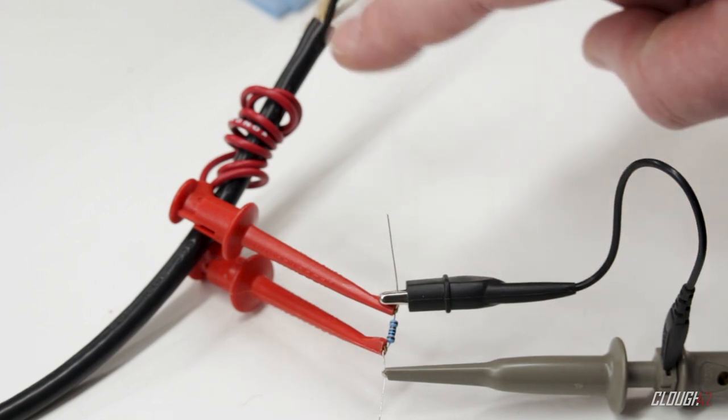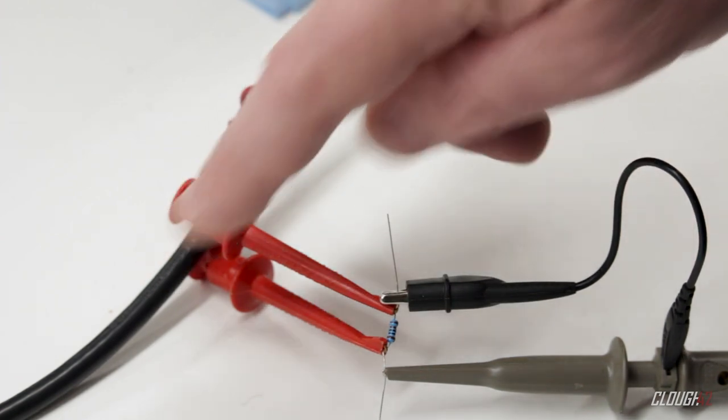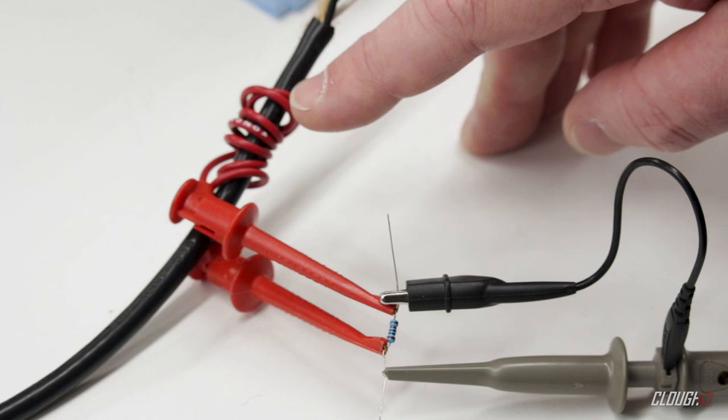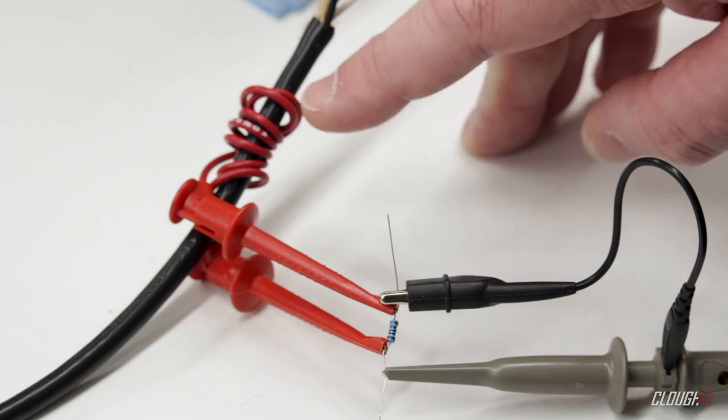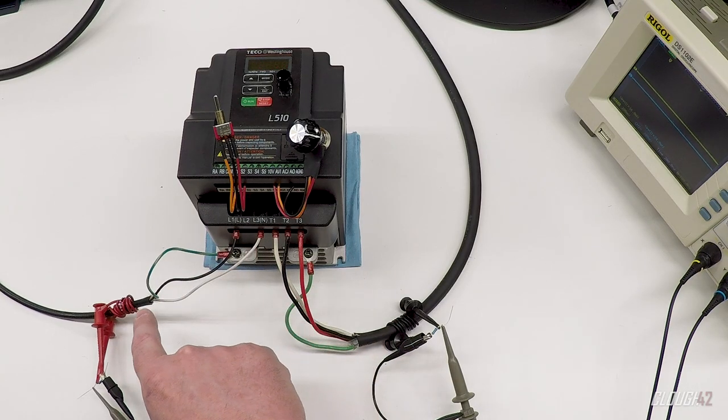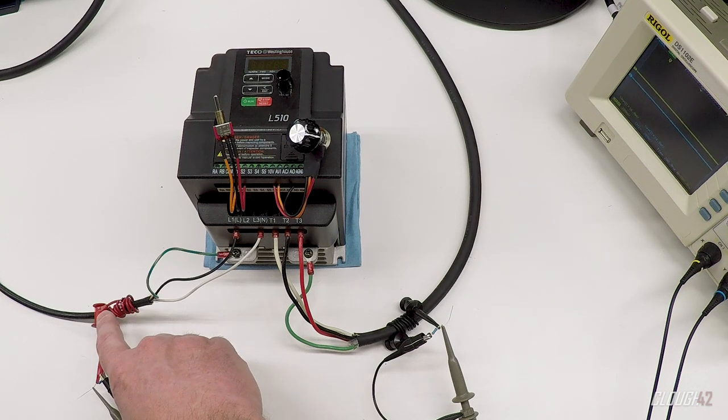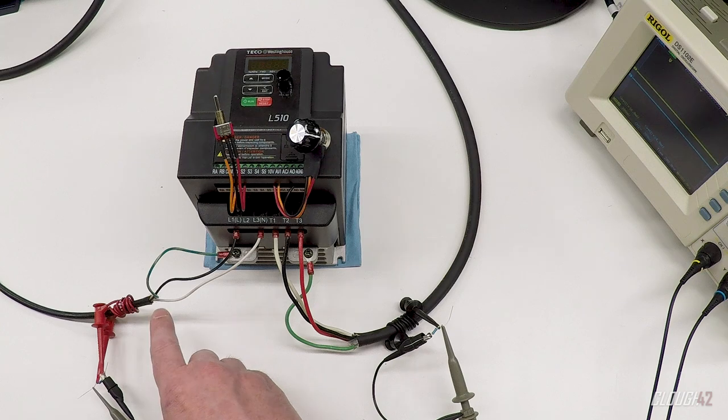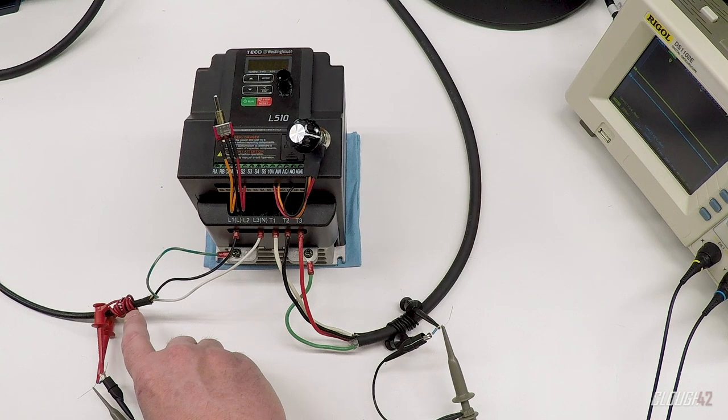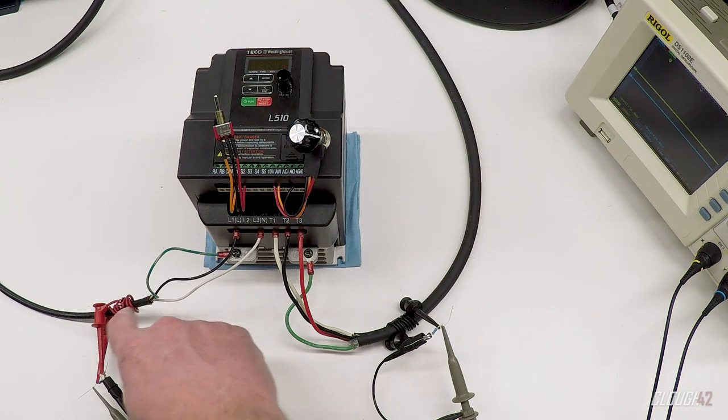Now the current flowing through the line cord here produces an electromagnetic field. And this coil of wire wrapped around it forms a transformer that induces a current in that coil from the magnetic field that's in this cable. Now because the hot and neutral lines are both inside the cable, we're only measuring the net magnetic field and the net current. The power that's actually going to the motor cancels out. So we shouldn't see that current in the current transformer. We should only see the noise current or the common mode current that's being transmitted back up this cable.